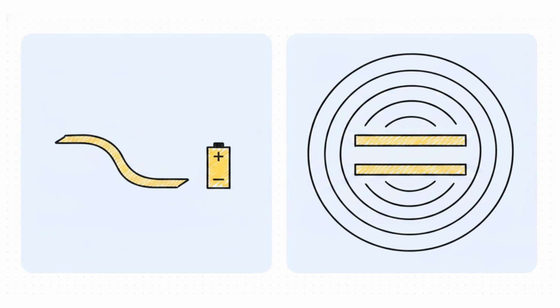The industry actively debates which is better, and really, it comes down to engineering trade-offs. PMUT uses piezoelectric thin films bending in a flexural mode. That gives it a lower electrical impedance, which is fantastic because it means simpler drive electronics and lower power consumption. On the flip side, CMUT, using that electrostatic air gap, generally gives you a broader operational bandwidth for better image resolution and superior pitch scaling so you can pack more sensors into a tighter space without crosstalk. Both are absolute game changers over old ceramic crystals.